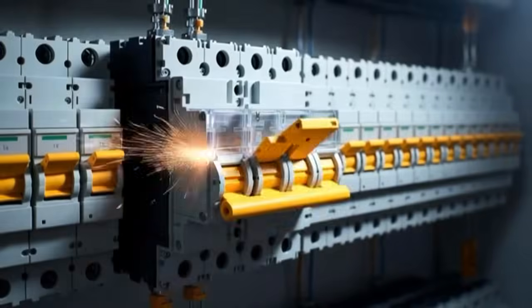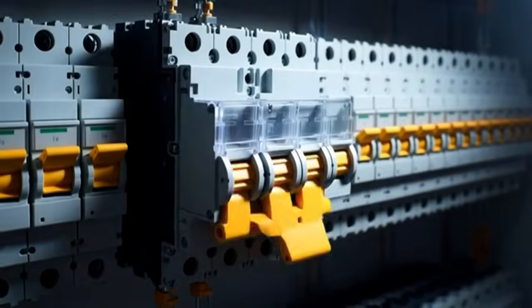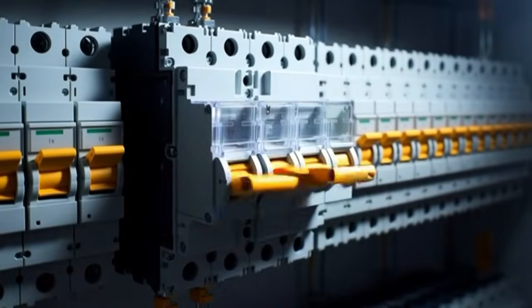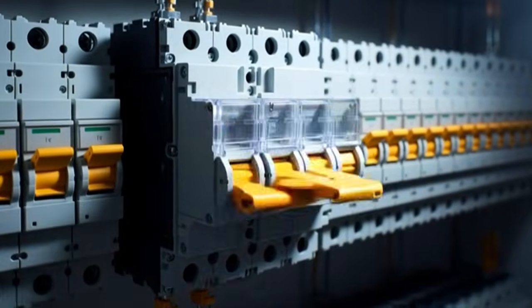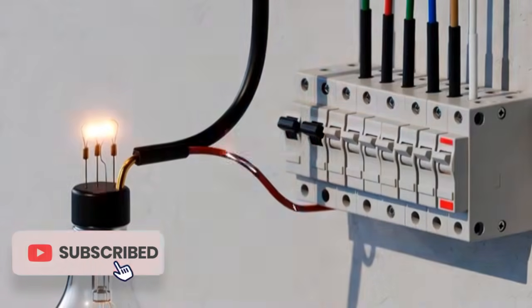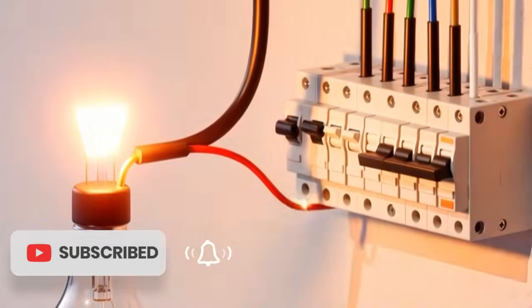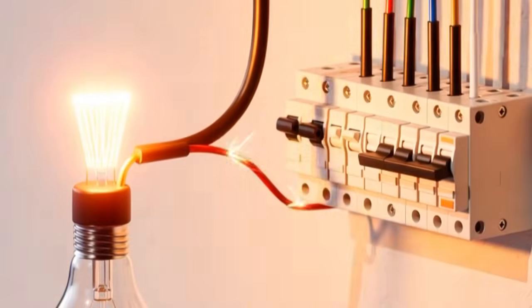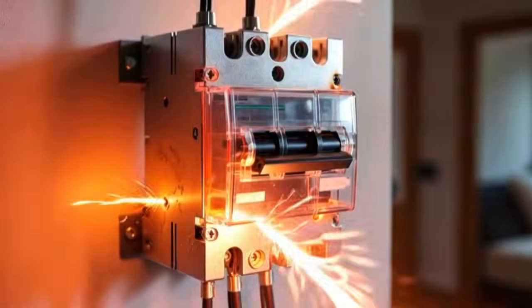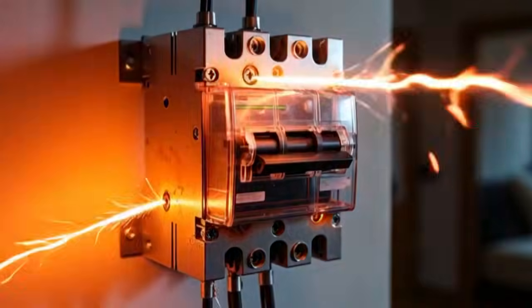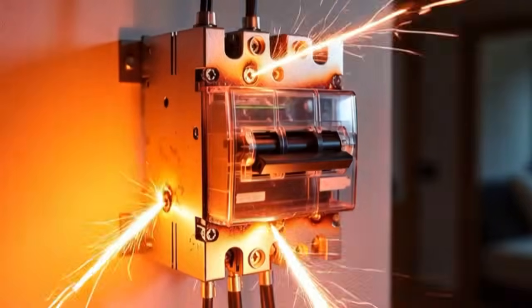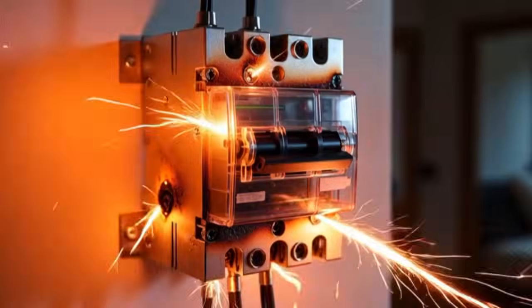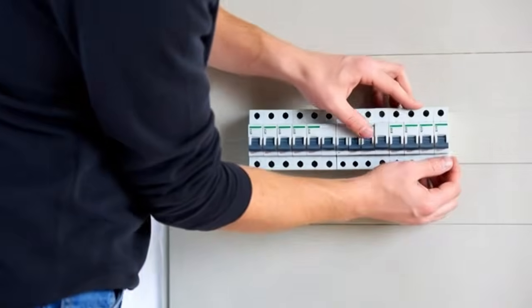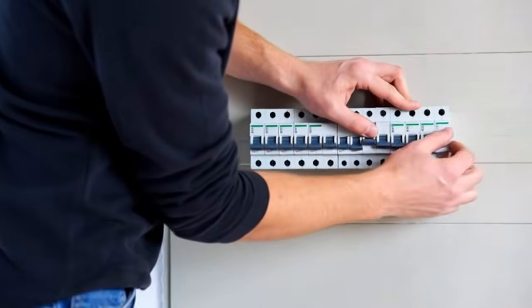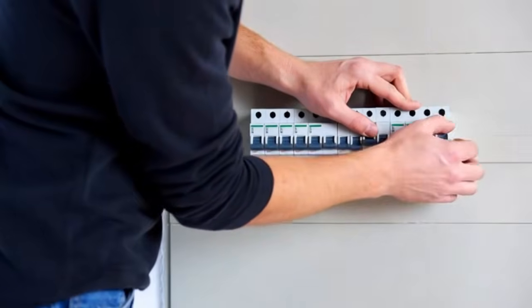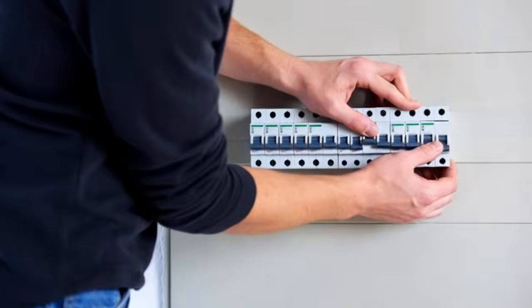Sometimes the problem isn't the circuit at all. Sometimes the breaker itself has failed. Circuit breakers are mechanical devices with a limited lifespan. After years of service and multiple trip cycles, the internal components wear out. Springs weaken, contacts pit and corrode. The bimetallic strip loses its calibration. The electromagnetic mechanism degrades. A failed breaker might trip under normal conditions when no fault exists, but a failed breaker can also refuse to reset even when the circuit is perfectly safe.